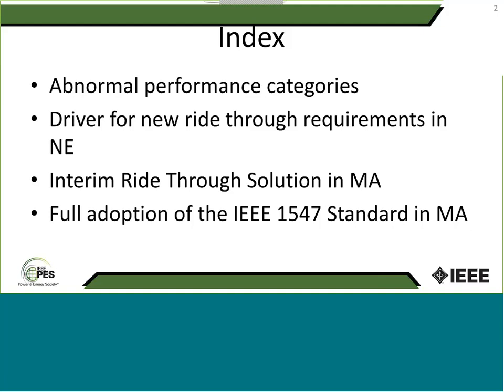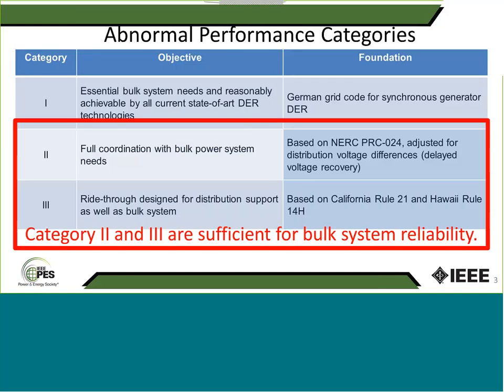First, you'll see the driver for some new ride-through requirements in New England, and also what was the interim solution in Massachusetts until we see a fully revised 1547.1 standard published. Until then, we really won't have any equipment that is certified by an NRTL that meets the 1547 requirements, but there is an interim solution that we implemented in Massachusetts to meet the ride-through requirements that were requested by ISO New England. And then finally, I'll also talk about the plan in Massachusetts on how to implement the rest of the standard, starting out with ride-through, then voltage regulation, frequency regulation, and so on. So moving on to the next slide.